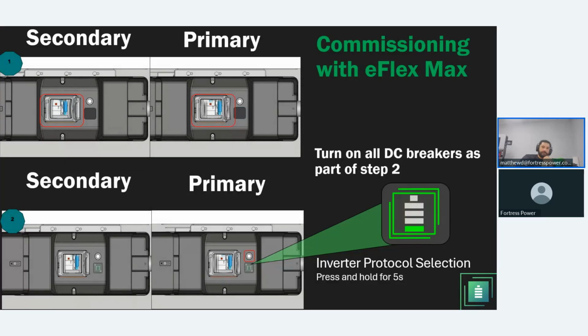Commissioning the eFlex Max is essentially the same thing. Flip on the DC breakers, the battery breaker, and the battery breaker on the inverter, and then you're going to press the push button on the primary battery, and that's going to light up the other batteries. And then you're going to select the protocol the same way that you do with the eBoost. Hold 5 seconds, and in this case, the eFlex Max lights up green, but you should see the same configuration.